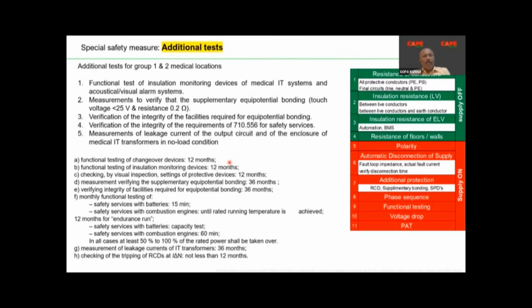The third point for medical locations is additional tests in group 0, group 1 and group 2 medical locations. See the second one: measures to verify the supplementary equipotential bonding, touch voltage less than 25 volt and resistance of all the wires lesser than 0.2 ohm. All these tests are actually very much mandatory. So I request all of you to go through these standards or these points. I can share the presentation, absolutely not a problem.